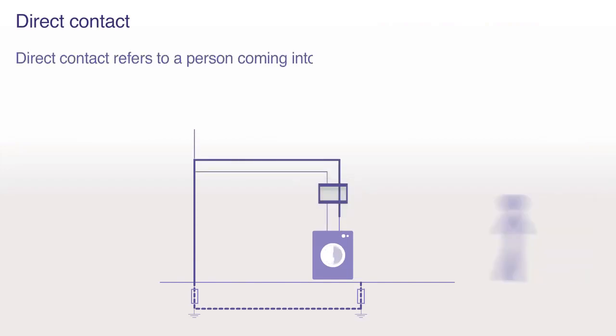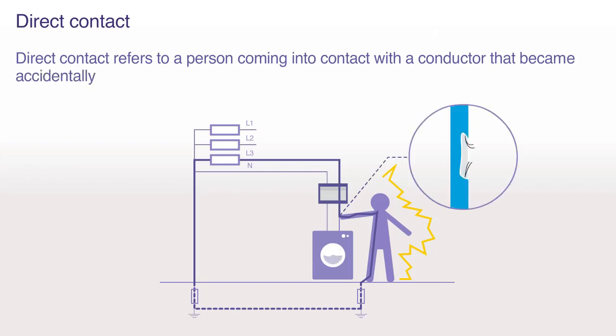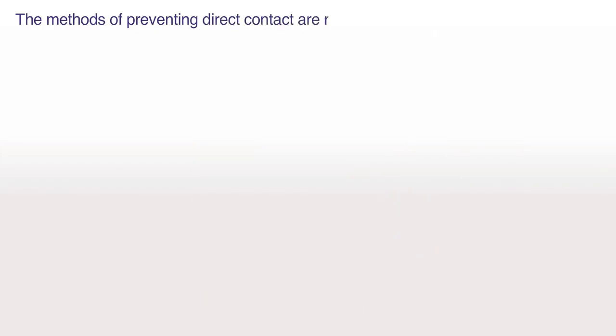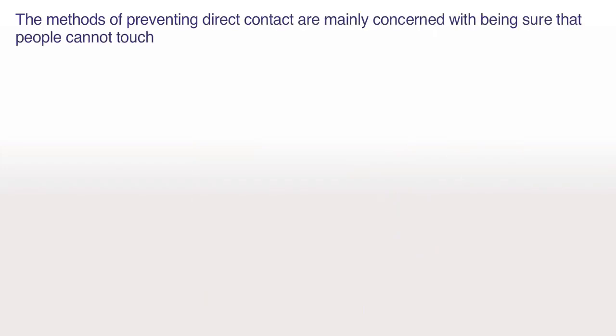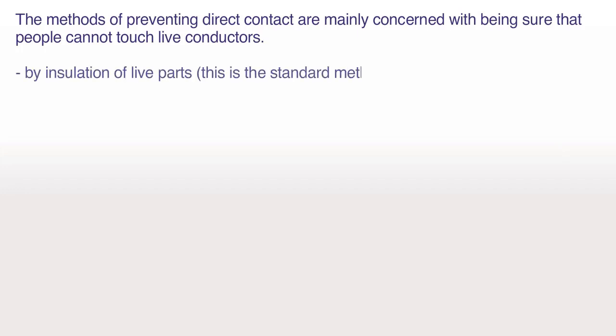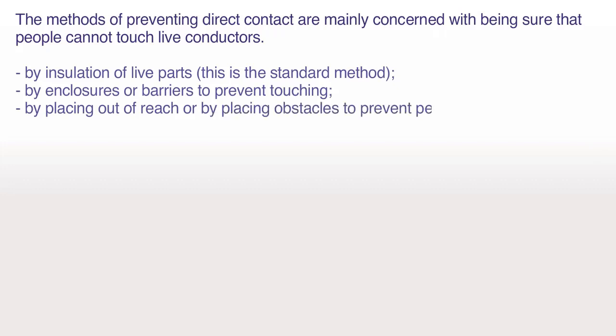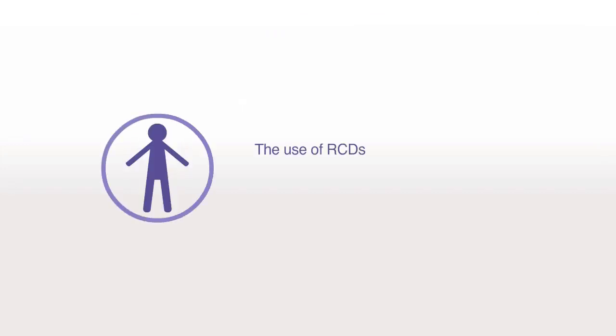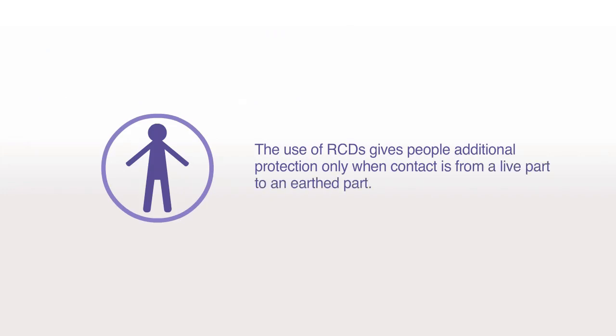Direct contact. Direct contact refers to a person coming into contact with a conductor that became accidentally accessible. The methods of preventing direct contact are mainly concerned with being sure that people cannot touch live conductors. By insulation of live parts. This is the standard method. By enclosures or barriers to prevent touching. By placing out of reach or by placing obstacles to prevent people from reaching live parts. The use of RCDs gives people additional protection only when contact is from a live part to an earthed part.